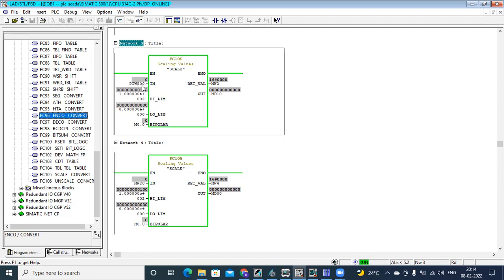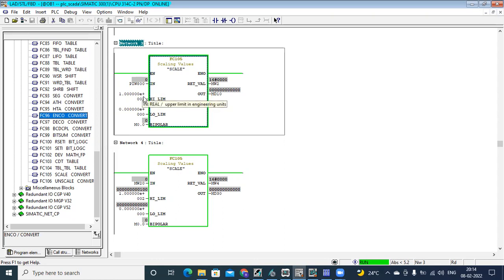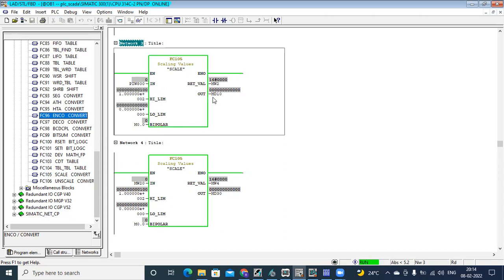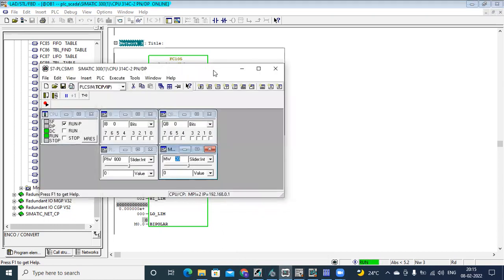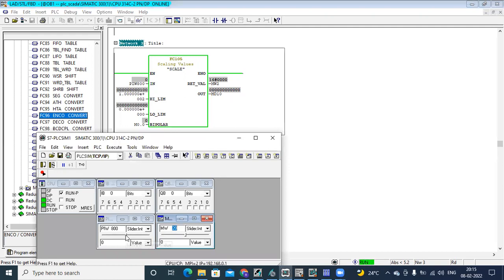That value will be coming here in PIW 800 — 800 is the address for the analog signal. In the PLC we will see how this addressing works. For our monitoring limit I have set 0 to 100, low limit and high limit. The values coming in are converted into 0 to 100, minimum 0, maximum 100. That result is displayed in the output called MD10. I have already made this logic to check the result using a simulator slider.